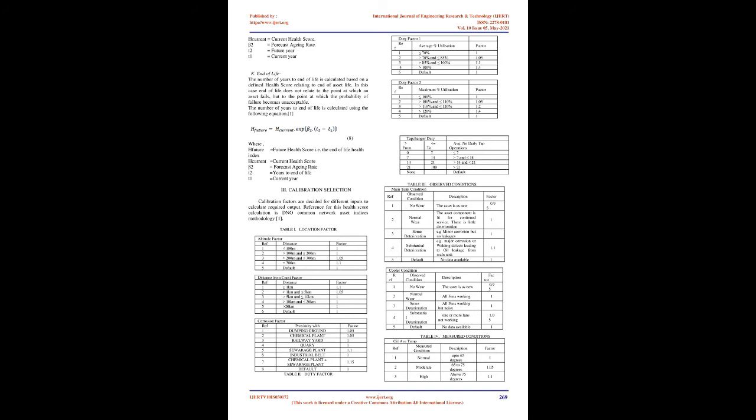The existing process of asset condition monitoring techniques involves monitoring dissolved gas analysis, oil screening test, FFA of oil, various testing results such as thermal image, partial discharge, sweep frequency response analysis, dielectric frequency response analysis, etc. Each individual parameter data stated above has a different effect on the transformer. This effect does not have a linear effect on transformer age. So this evaluation method for deciding present health status of the transformer is not enough.